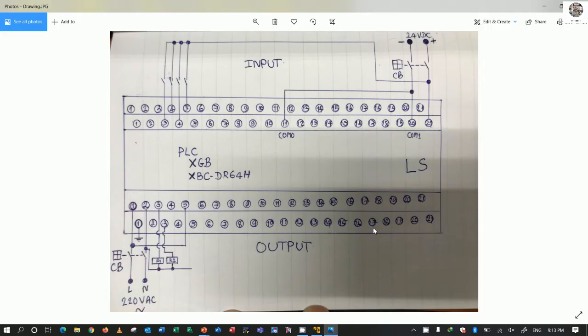Here is the PLC XBC-DR64H. I have already connected the power supply to terminal number one and number two because it is 220V AC. I have connected the cable from the input side, and we need to supply 24 volts to terminal 20 and terminal 21. For input, we can connect 24 volts to the contact and then connect to terminal number 3, which is input number 0.